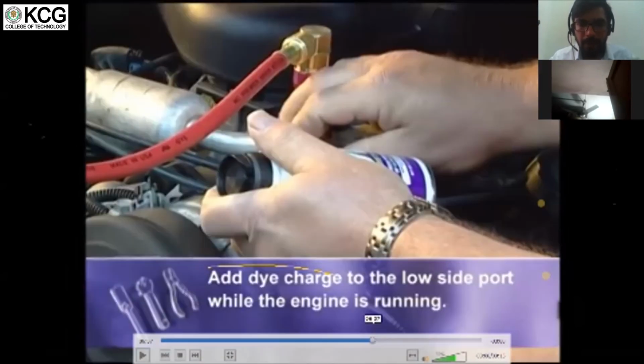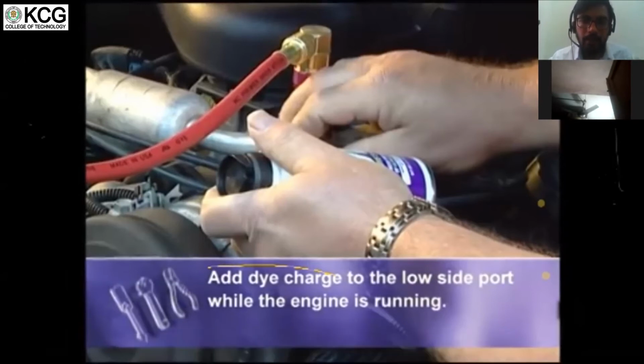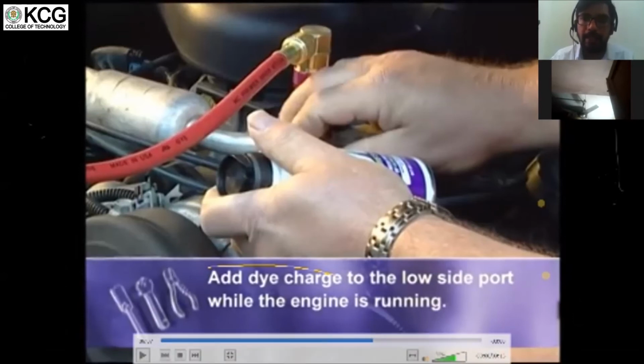I've got a leak right at the body of the yellowish, which is showing. This is the leak in this system. So this is how, with the UV dye, you can diagnose where the leak is. So, back to our presentation.